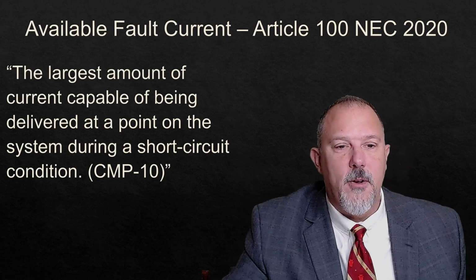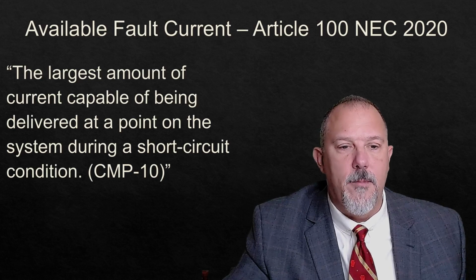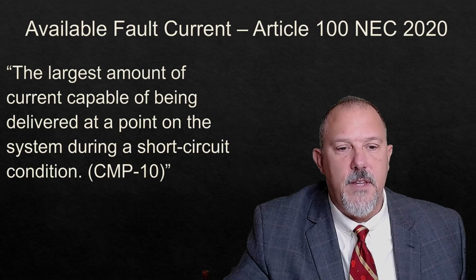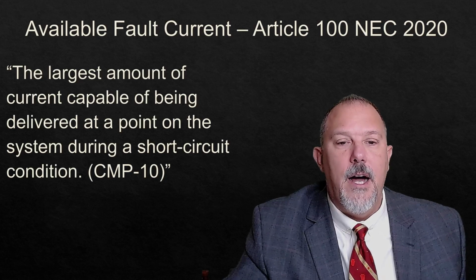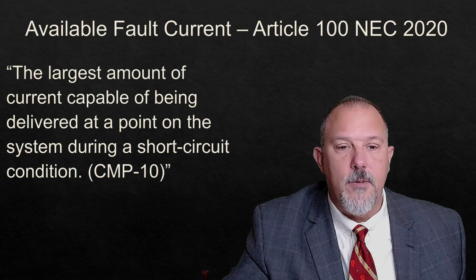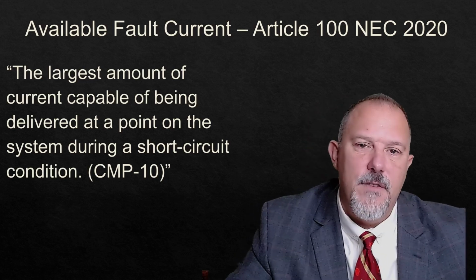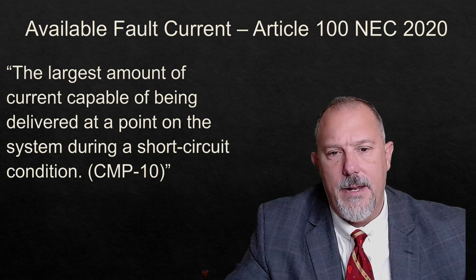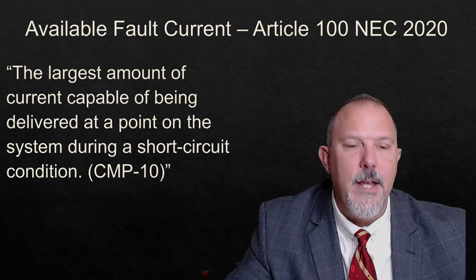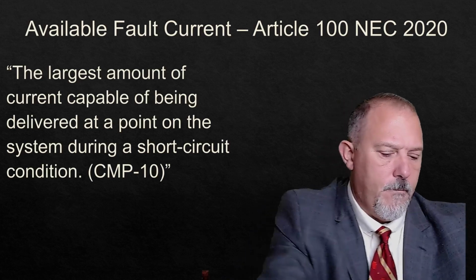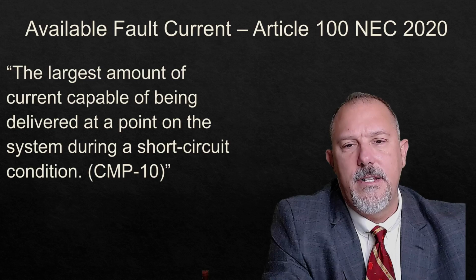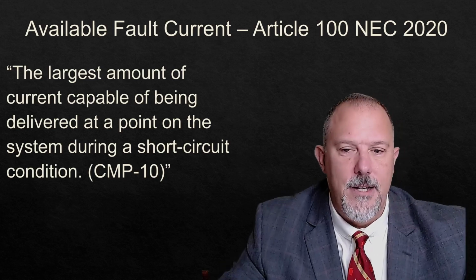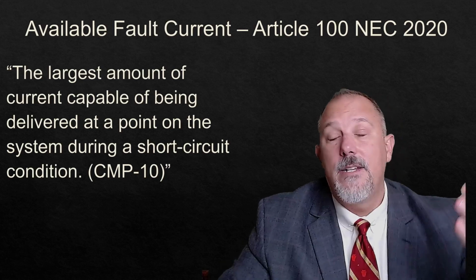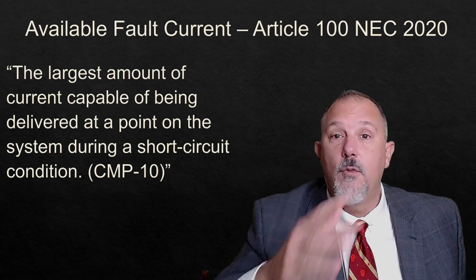Equipment intended to interrupt current at fault levels shall have an interrupting rating at nominal circuit voltage at least equal to the current that is available at the line terminals of the equipment. Equipment intended to interrupt current at other than fault levels shall have an interrupting rating at nominal circuit voltage at least equal to the current that must be interrupted. That didn't have the maximum number in there that I thought was in there. That's not a good... Let me find a good reference section. Here we go. 110.24. What am I talking about? Yeah, 110.24 is a good example.